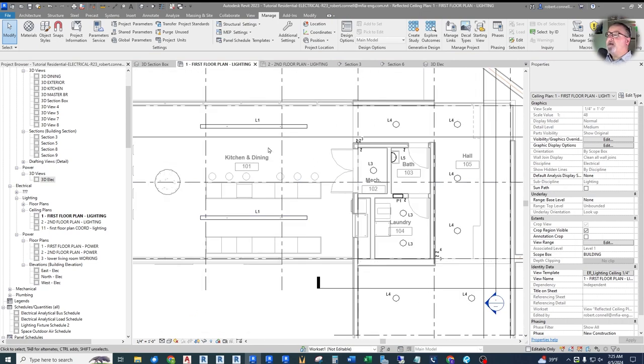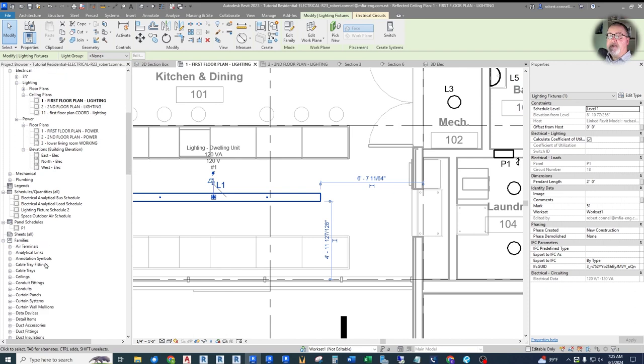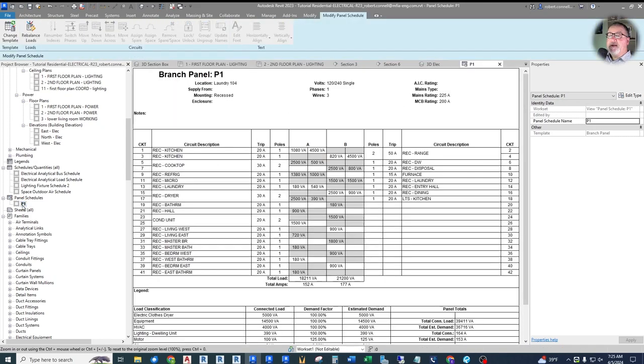To confirm circuiting, click on a light and check its instance parameters — under load, you'll see panel P1 and the circuit number. Revit automatically assigns the next available circuit based on rules you've set up. Let's open our panel schedule from the project browser under panel schedules. Here you can see 'Lights Kitchen' on circuit 18 as a 20-amp circuit with 390 watts on it — plenty of room to add more lights.